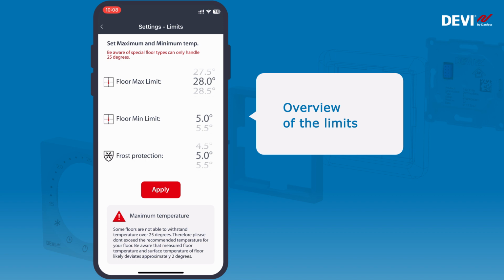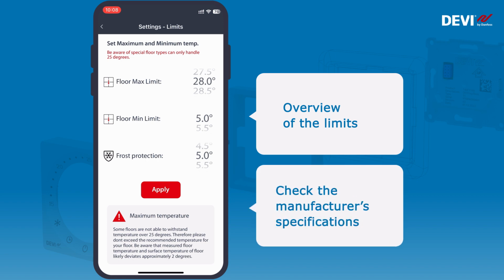Once we apply something, it will be asked if we really want to do this, because some of these things can hurt your floorings. Some hardwood floors cannot take more than a maximum temperature of 27 degrees. So please take care and ensure that this is in accordance with manufacturer specifications.